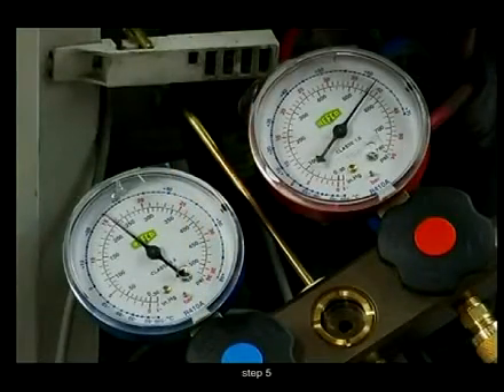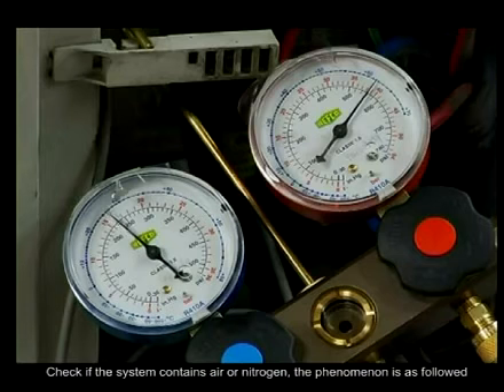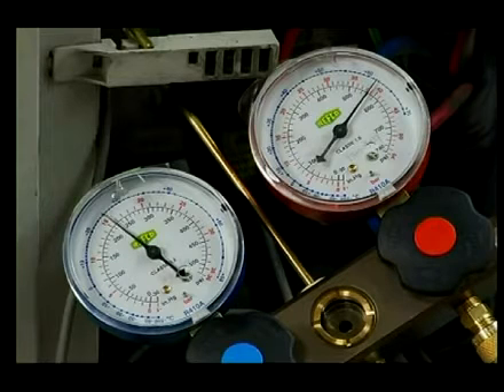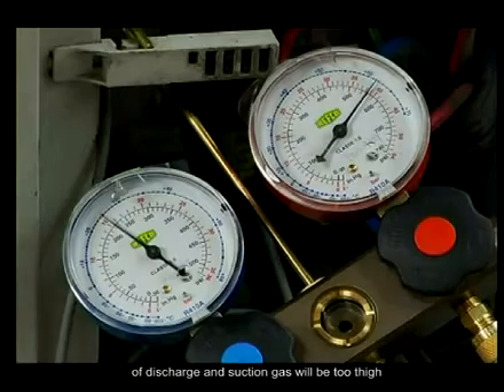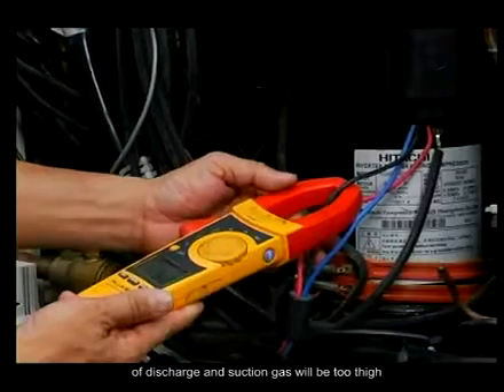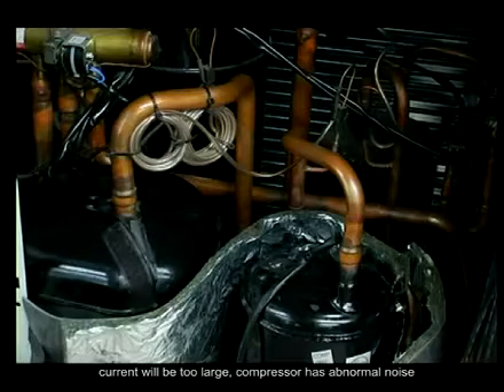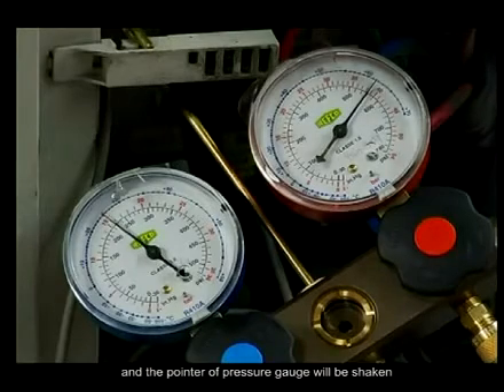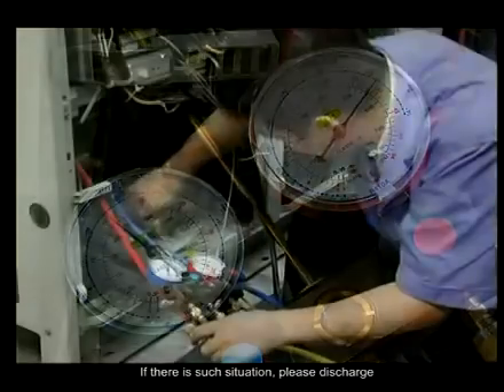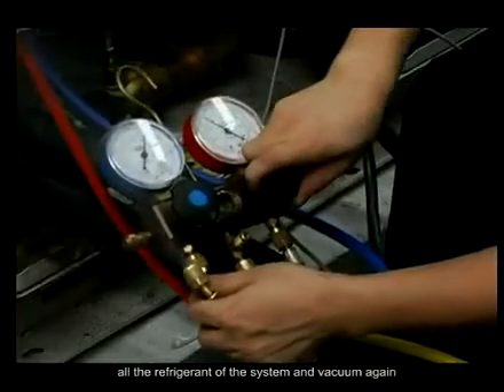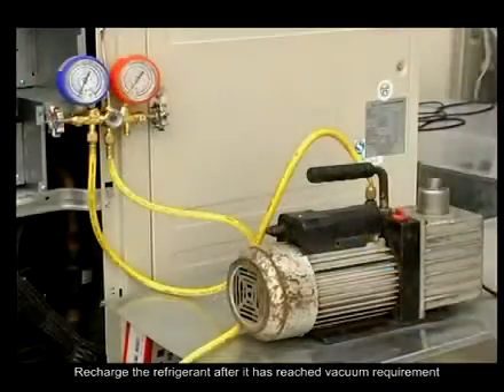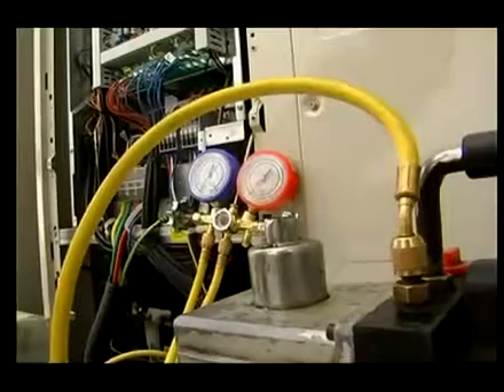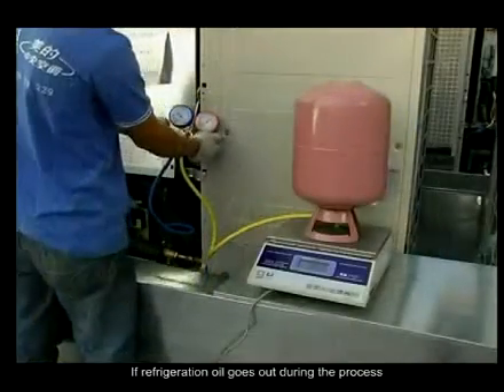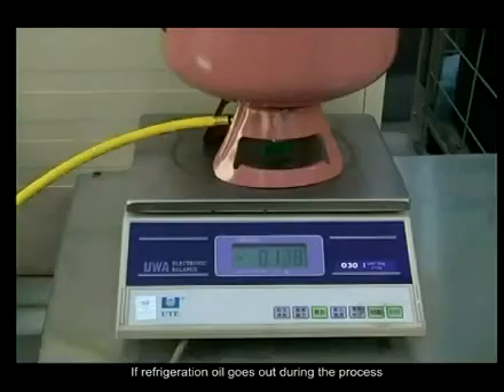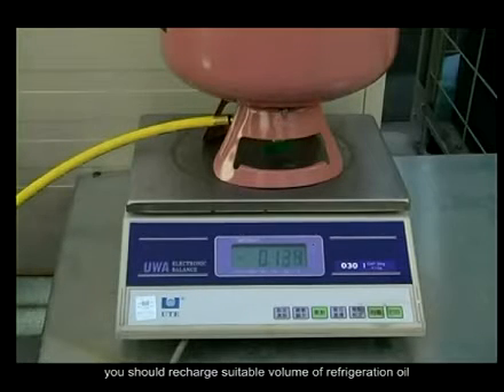Step 5. Check if the system contains air or nitrogen. The phenomenon is as follows. When it is running, the pressure and temperature of the discharge and suction gas will be too high. Current will be too large. The compressor has abnormal noise, and the pointer of the pressure gauge will shake. If there is such a situation, please discharge all the refrigerant of the system and vacuum again. Recharge the refrigerant after it has reached the vacuum requirement. If refrigeration oil goes out during the process, you should recharge a suitable volume of refrigeration oil.